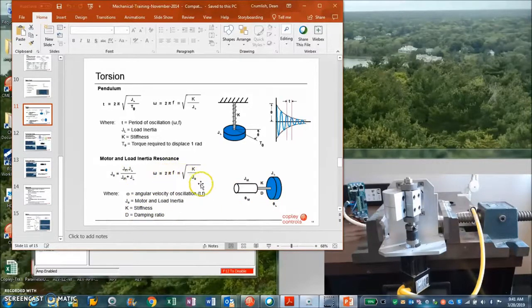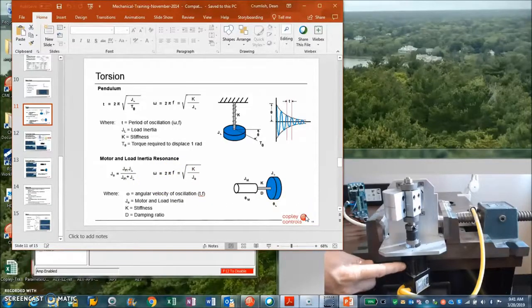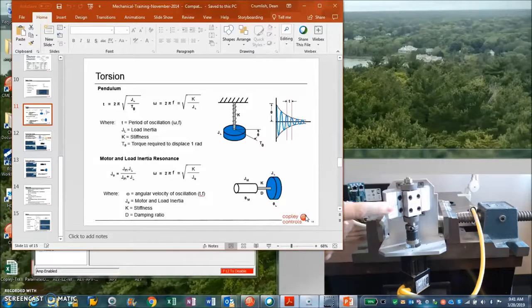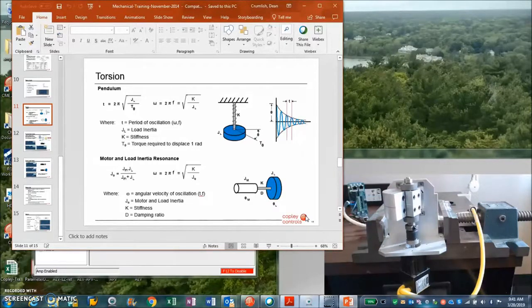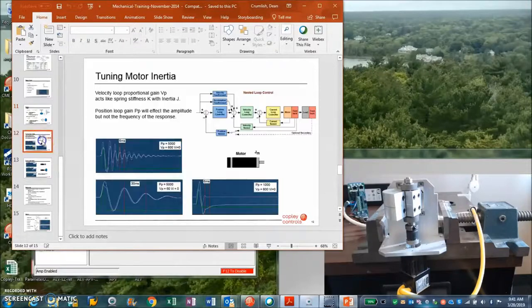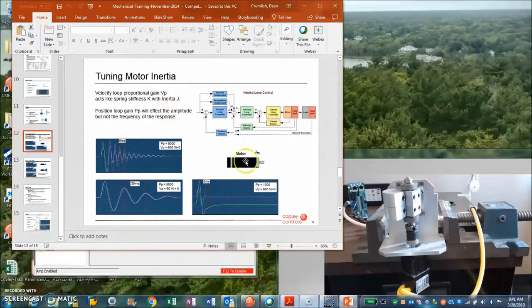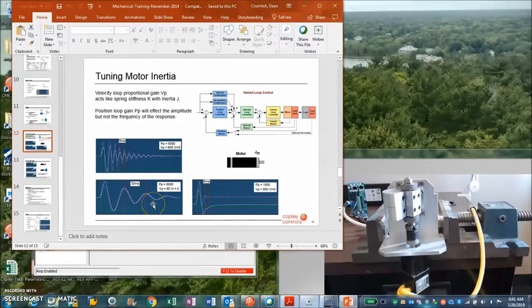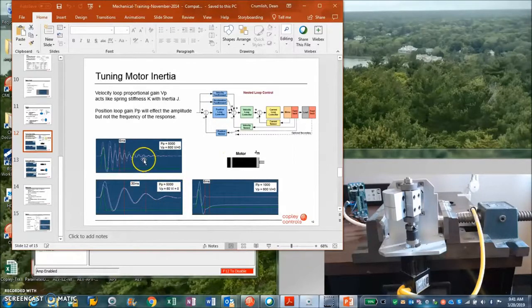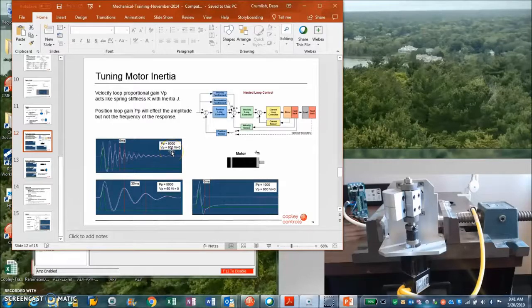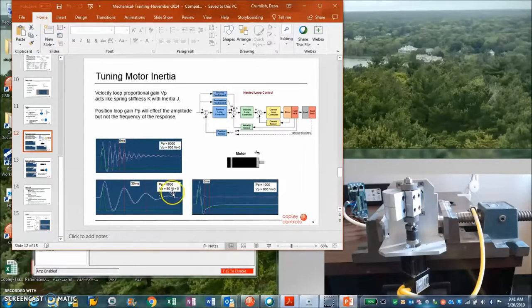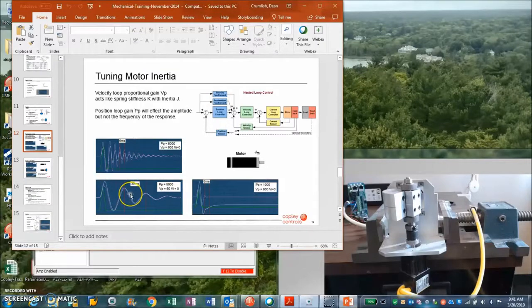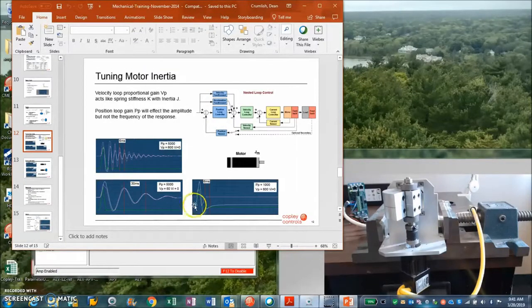There's a damping ratio, so there's a frequency at which it will settle out. The same thing is true here for the electromechanical time constant. I'm trying to hold the motor shaft, I'm pulling back on the load, I'm letting go, and it responds at the electromechanical frequency. In a system, we use the loops to control the velocity and position, and what you'll notice is the velocity stiffness. A higher VP has a higher frequency versus a lower VP that has a lower frequency, so the frequency is dependent on the stiffness of the velocity loop.